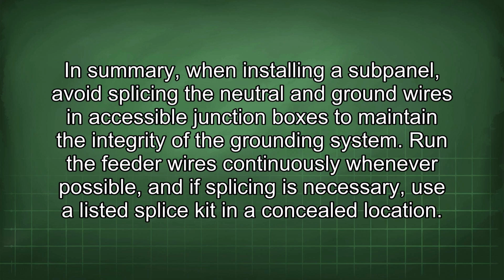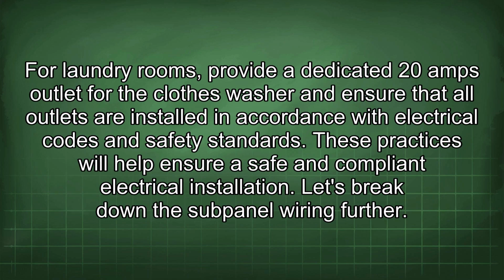In summary, when installing a subpanel, avoid splicing the neutral and ground wires in accessible junction boxes to maintain the integrity of the grounding system. Run the feeder wires continuously whenever possible, and if splicing is necessary, use a listed splice kit in a concealed location. For laundry rooms, provide a dedicated 20 amp outlet for the clothes washer and ensure that all outlets are installed in accordance with electrical codes and safety standards. These practices will help ensure a safe and compliant electrical installation.